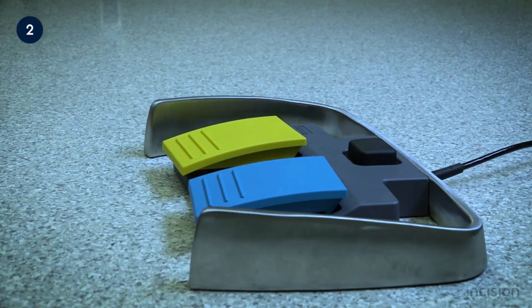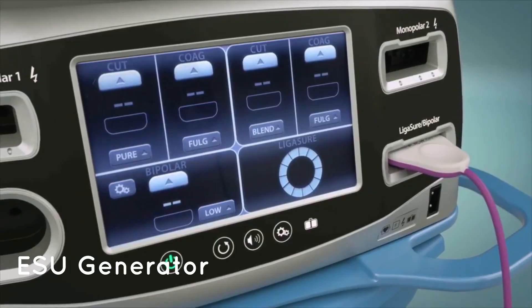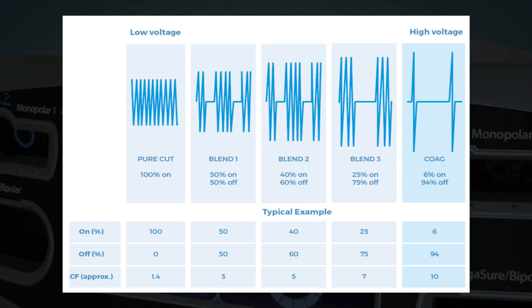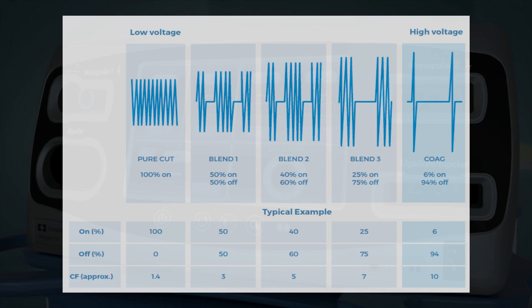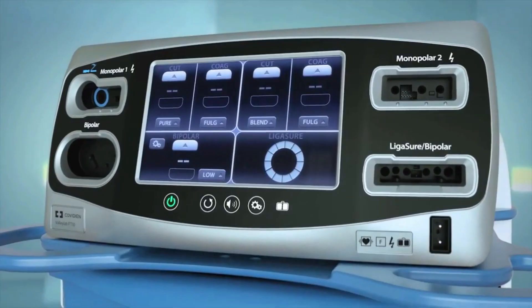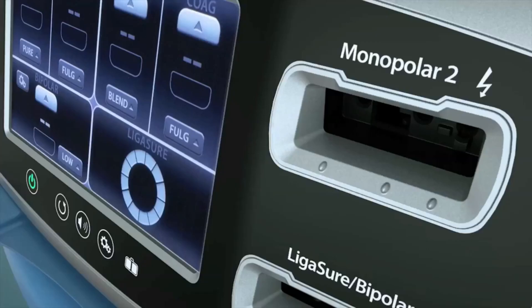ESU generators are able to produce a variety of waveforms. As waveforms change, so will the corresponding tissue effects. Using a constant waveform, like cutting, the surgeon is able to vaporize or cut the tissue — these waveforms produce heat very rapidly. Using an intermittent waveform, like coagulation, causes the generator to modify the waveform so that the duty cycle is reduced. This interrupted waveform will produce less heat; instead of tissue vaporization, a coagulum is produced.